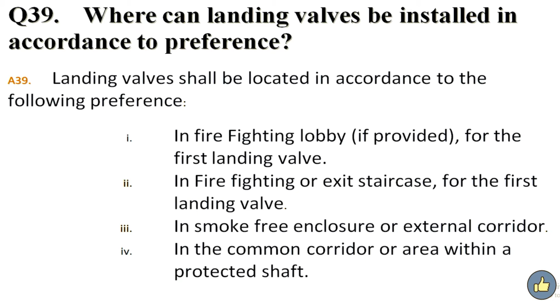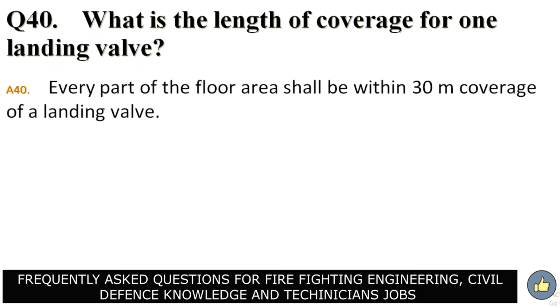Where can landing valves be installed in accordance to preference? Answer. Landing valve shall be located in accordance to the following preference. 1. In firefighting lobby, if provided, for the first landing valve. Second, in firefighting or exit staircase for the first landing valve. Third, in smoke-free enclosure or external corridor. 4. In the common corridor or area within a protected shaft. What is the length of coverage for one landing valve? Answer. Every part of the floor area shall be within 30 meters coverage of a landing valve.